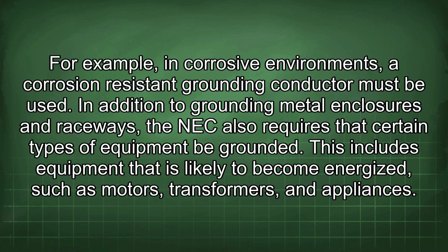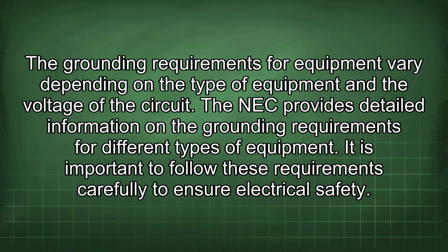In addition to grounding metal enclosures and raceways, the NEC also requires that certain types of equipment be grounded. This includes equipment that is likely to become energized, such as motors, transformers, and appliances. The grounding requirements for equipment vary depending on the type of equipment and the voltage of the circuit. The NEC provides detailed information on the grounding requirements for different types of equipment. It is important to follow these requirements carefully to ensure electrical safety.